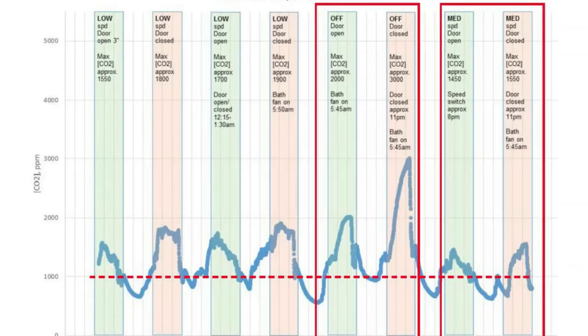This chart shows the master bedroom set on low speed, off, and on medium speed. The system is not able to keep up on low or medium speed, regardless of the door open or closed position, but it does perform much better on medium speed than when off completely. Now let's take a look at the kids' rooms.